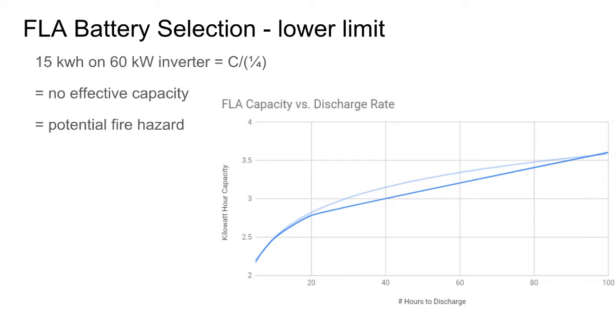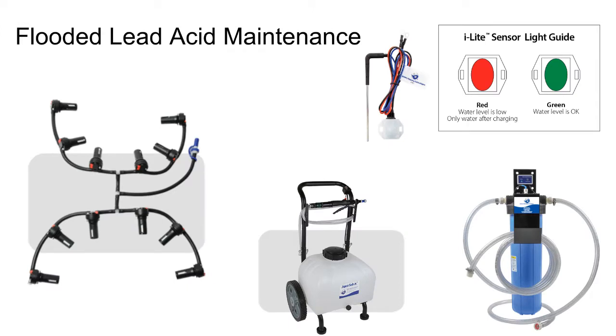You know, the point is with your lead-acid batteries, they're really not even good enough for load leveling unless you need to load level for a period of 5 hours or more. If you're trying to load level in the morning for 2 hours and then charge your battery back up and then load level in the evening for 2 hours, at that point, lithium ion's the better choice. Personally, I think a combination of the two is the better choice.